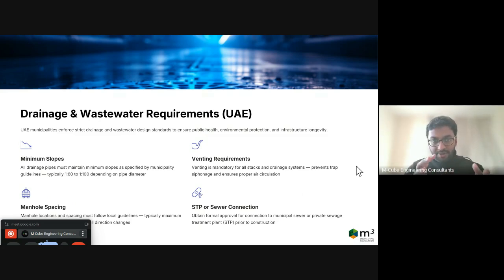Some key requirements: maintain the minimum slopes defined by the authority, venting requirements with first and last manhole vented properly, proper traps provided, manhole spacing with maximum requirements that cannot be exceeded, and depth. If the depth of the manhole changes, the shape of the manhole changes.